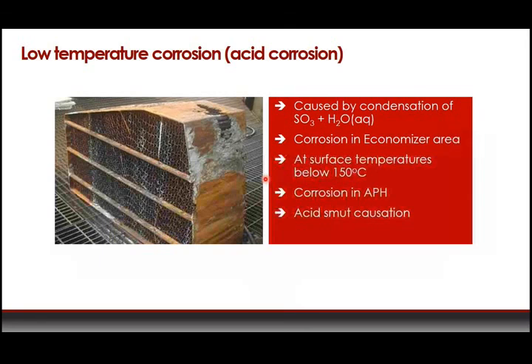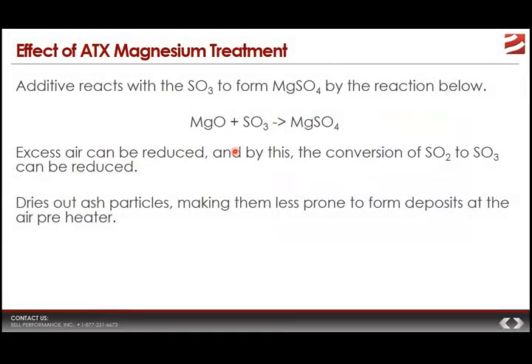An example of low temperature corrosion in an economizer shows significant corrosion damage caused over time by condensation of sulfuric acid onto the equipment — it will have to be replaced. This happened in the economizer area when the surface temperature of the metal was below 150 degrees — below the likely dew point for that particular stream. The magnesium in ATX reacts with SO3 that had been formed, neutralizes it, and turns it into harmless magnesium sulfate.